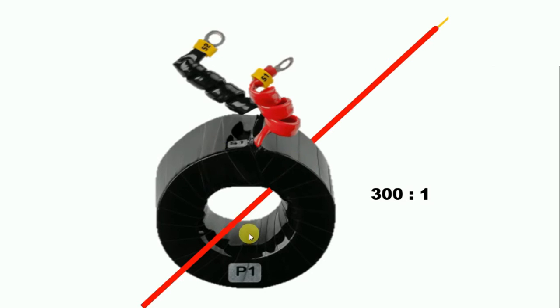and the CT will work as secondary winding. Let's suppose right now in this wire, 300 ampere current is flowing. So in secondary terminals, 1 ampere current will flow.